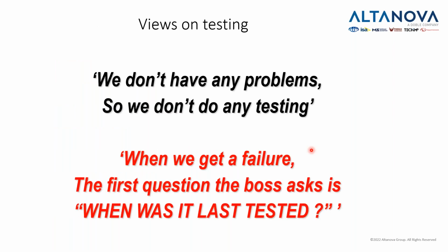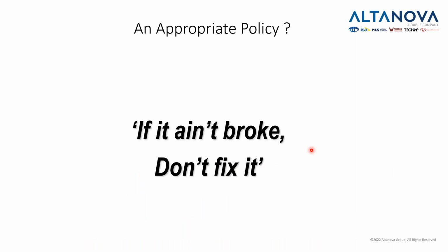So some views on testing. Very often we hear, we don't have any problems, so we don't do any testing. But the problem is that when we get a failure, the first question the boss asks is, when was it last tested? So it is important to maintain your transformer the same way, for example, like it's important to maintain the good health of your body, because we are all happy when we are healthy, but we start to focus on our issues when we start having issues with our health. The same can be applied for a transformer.